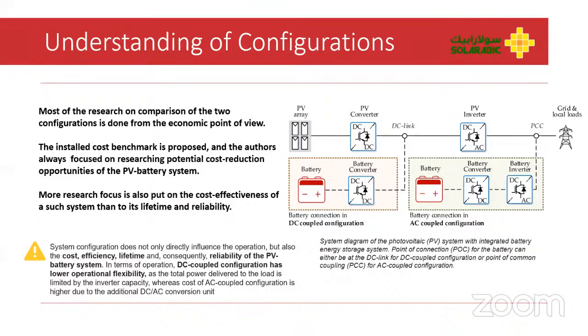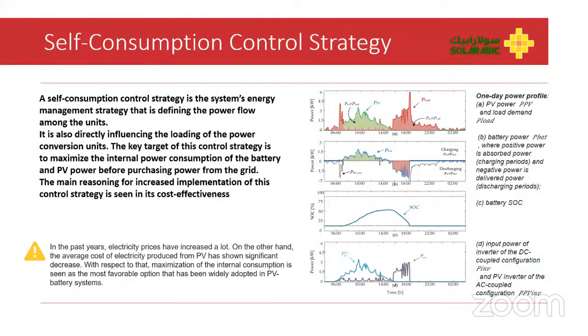In the DC coupled configuration, the flexibility for the operation is quite limited because there is only one DC to AC conversion unit, which is your inverter. But in the AC coupled configuration, the operational flexibility is more because you have two DC to AC conversion units, the inverter and the battery inverter. When we talk about the PV and the battery system, we normally talk about the self-consumption control strategy. The self-consumption control strategy is the system's energy management strategy that defines the power flow among the units. It also directly influences the loading of the power conversion units, which is very important in order to understand the reliability of any photovoltaic battery system.